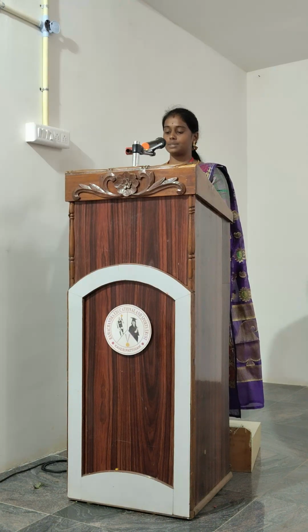In home installations, earthing is primarily focused on human safety. Every modern household contains numerous electrical appliances: refrigerators, washing machines, air conditioners, microwave ovens, water heaters, computers, and more. These appliances operate at voltages that can be dangerous if a fault occurs. Suppose an internal insulation failure causes the metal body of a washing machine to become live. Without proper earthing, touching the appliance could result in a serious electric shock. However, if the body is properly connected to earth, the fault current flows directly to the ground through a low resistance path. This causes protective devices such as circuit breakers or residual current devices (RCDs) to trip instantly, disconnecting the power supply and preventing harm.